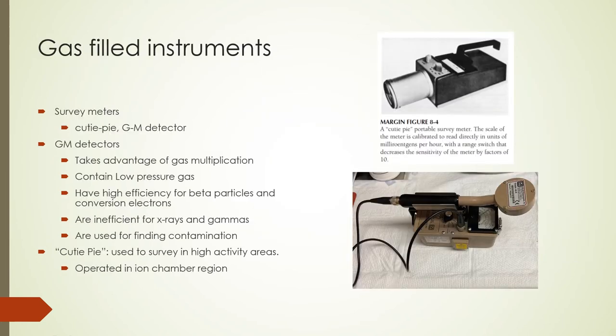Another important gas-filled instrument is the survey meter. Two survey meters used in nuclear medicine are the GM detector and the Cutie Pie detector. The GM detector is operated in the GM region where there is gas multiplication due to the avalanche effect, so very little external amplification is needed. The GM detector is high efficiency because of the high applied voltage. It can detect energetic beta particles and conversion electrons, and is often used for room contamination surveys, personnel monitoring, and detecting low levels of radioactivity. It is operated in pulse mode and acts as a paralyzable detector unless measures are taken. The Cutie Pie survey meter is used to monitor areas of high radioactivity and is operated in the ion chamber region in current mode.